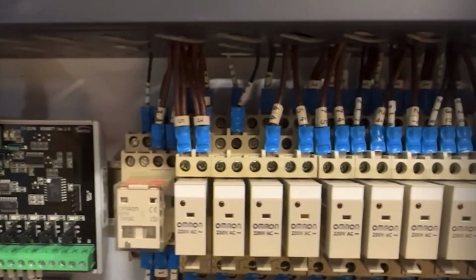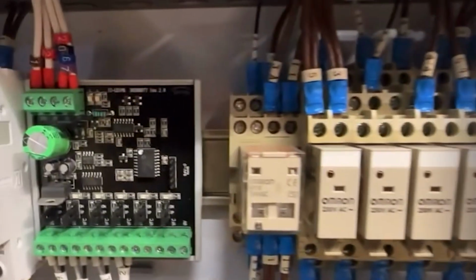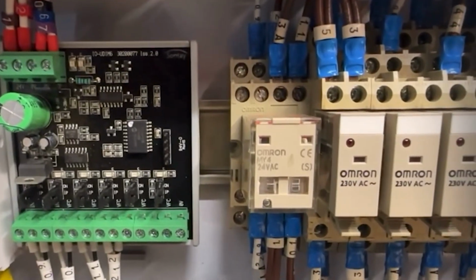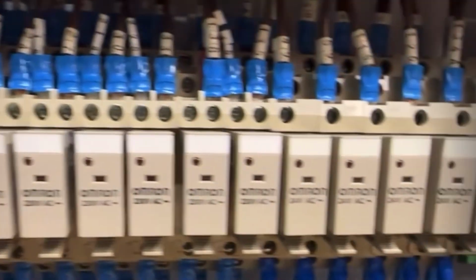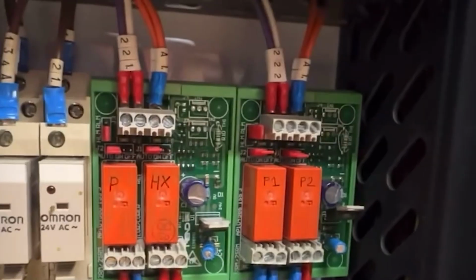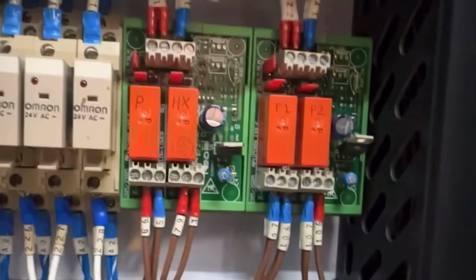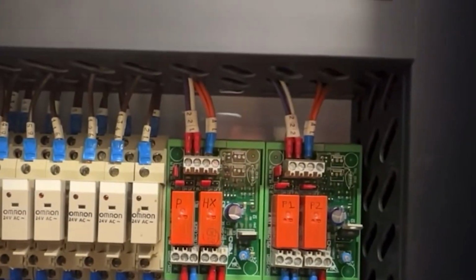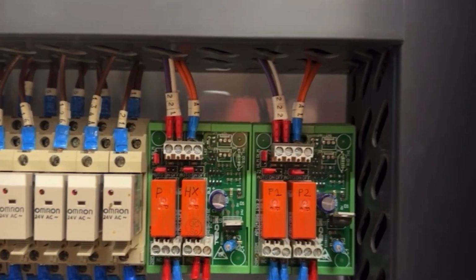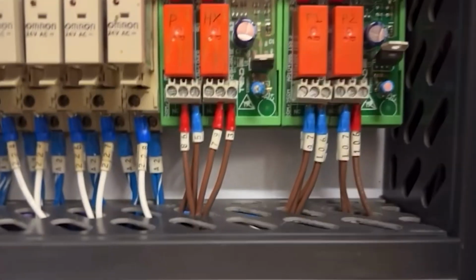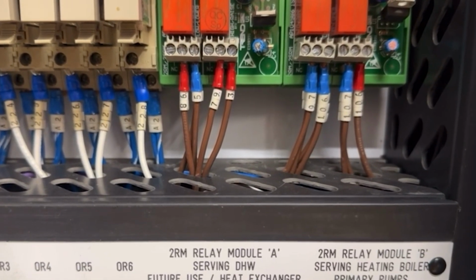Then we've got a massive bank of relays for controlling stuff, starting off with the 24 volt AC Omron that's obviously been changed. All the other ones are existing because Omron will last a lifetime. Then we've got two more of those cards that look like they're on a different sort of data bus, with different coloured wires. They've got relay switches on the outgoing: 2RM relay module A, 2RM relay module B. So yeah, that's that row and all the gubbins inside it.